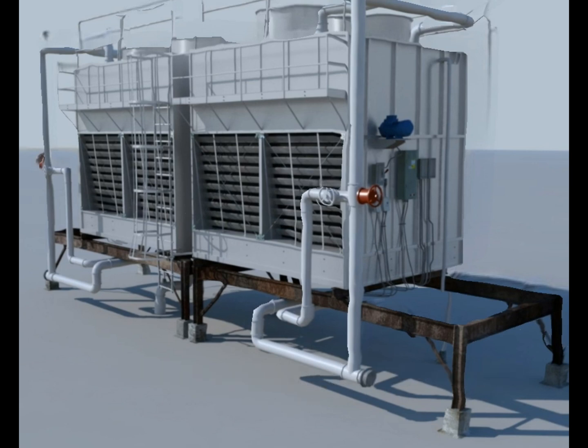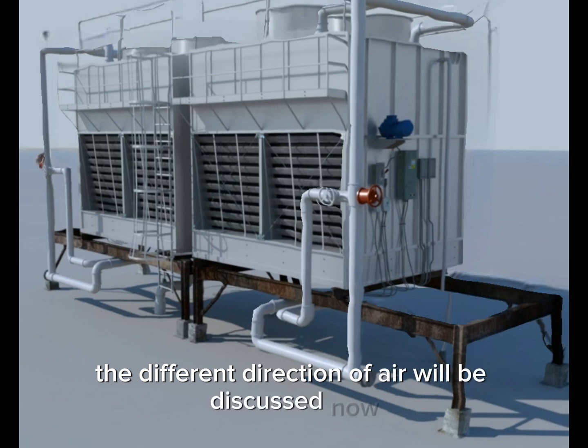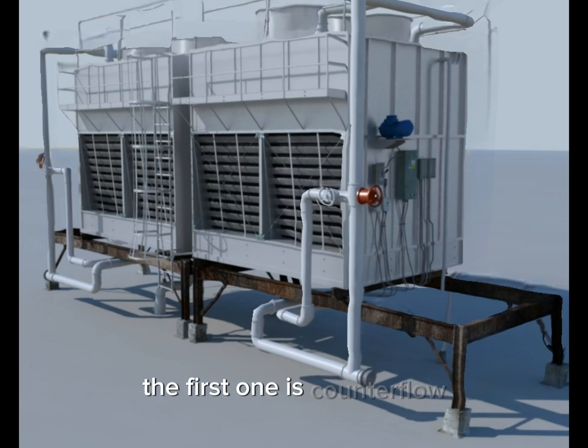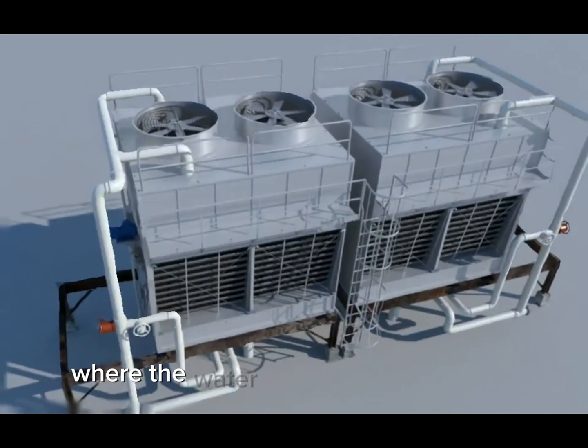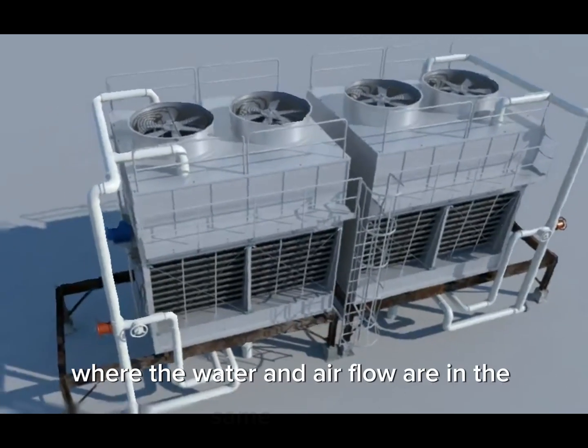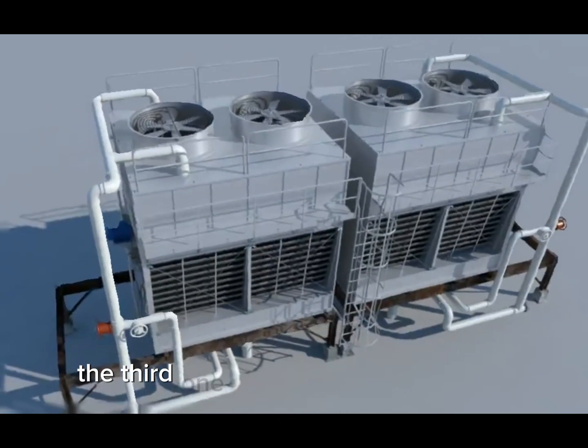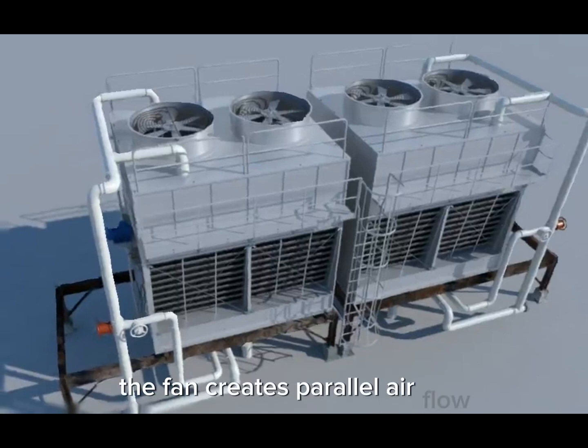The different directions of air flow will now be discussed. The first is counterflow, where the water and air supply move in different directions. The second is parallel flow, where water and air flow in the same direction. The third and last is cross flow, where water drips across the air chamber in an induced draft cooling tower, and the fan creates parallel air flow.